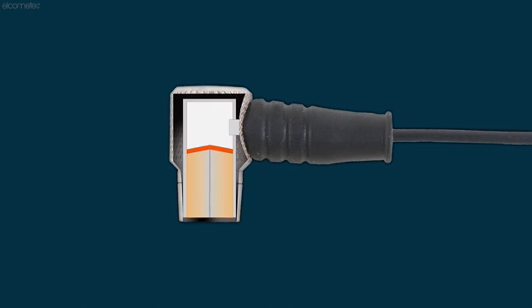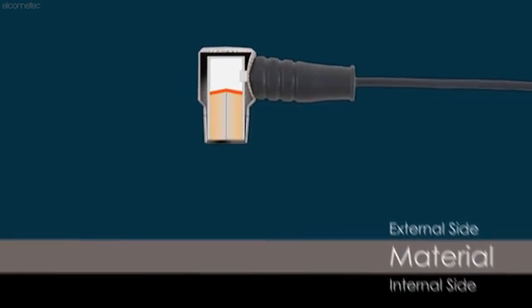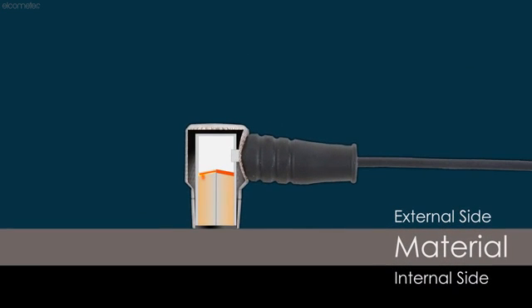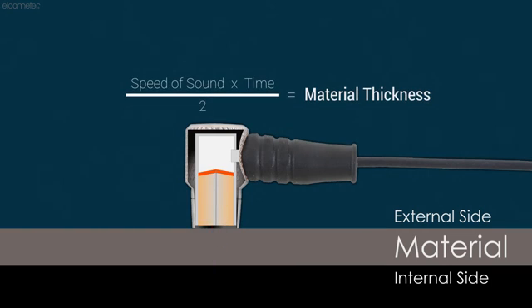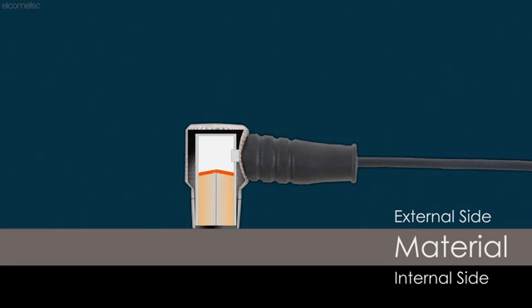Dual-element transducers consist of 2 independent crystals, separated by an acoustic barrier. The 2 elements are angled so that when one crystal emits an ultrasonic pulse, the energy path creates a V-shape, hitting the back wall of the material and echoing back towards the other crystal where it's detected. The gauge then uses the speed of the pulse and the time taken to travel from one crystal to another, from pulse to echo, to calculate the thickness of the material, with the acoustic barrier preventing any sound reaching the receiver directly from the emitter before the pulse has completed its path.